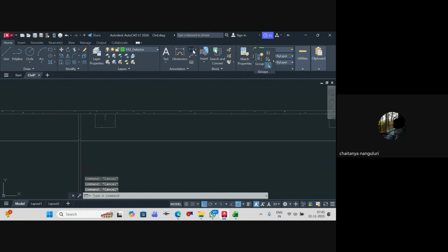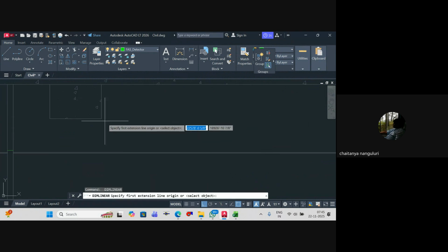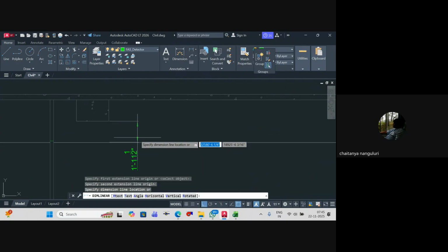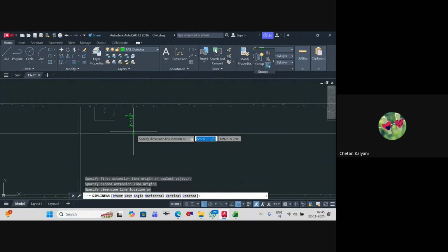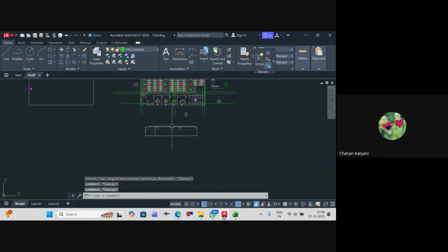So now if I wanted to place your detector, beam here, you can see it. What is the height I have? This height is only 3 feet. In that, this particular beam, the height is how much? Sorry, height of the beam, I have to mark it. Really sorry. So height of the beam is 2 feet. So in 3 feet, 2 feet means greater than 10% or not? Definitely, sir. Yes or no?